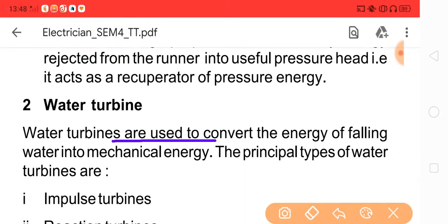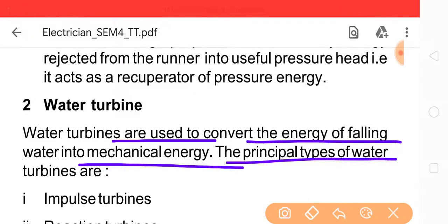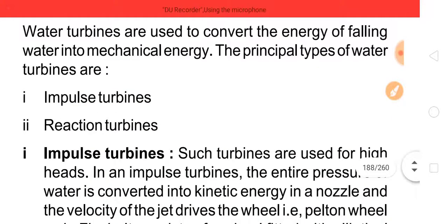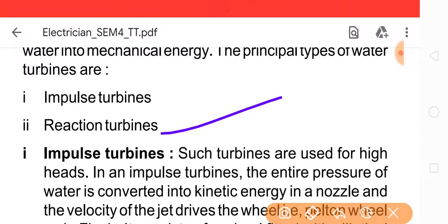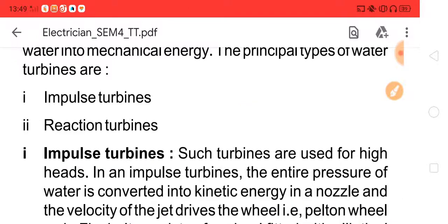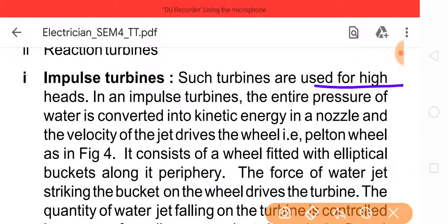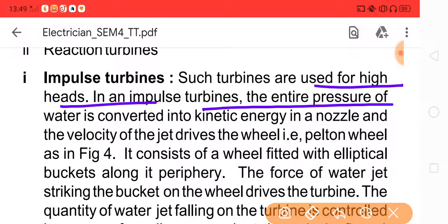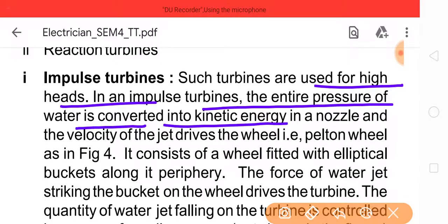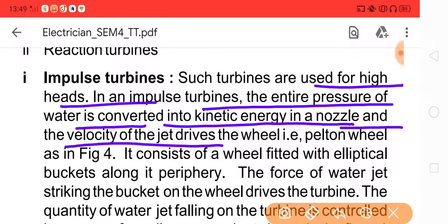Water turbines are used to convert the energy of falling water into mechanical energy. The principal types of water turbines are impulse turbines, followed by reaction turbines. Impulse turbines are used for high head. In an impulse turbine, the entire pressure of water is converted into kinetic energy in a nozzle and the velocity of the jet drives the wheel. A Pelton wheel is shown in the picture.